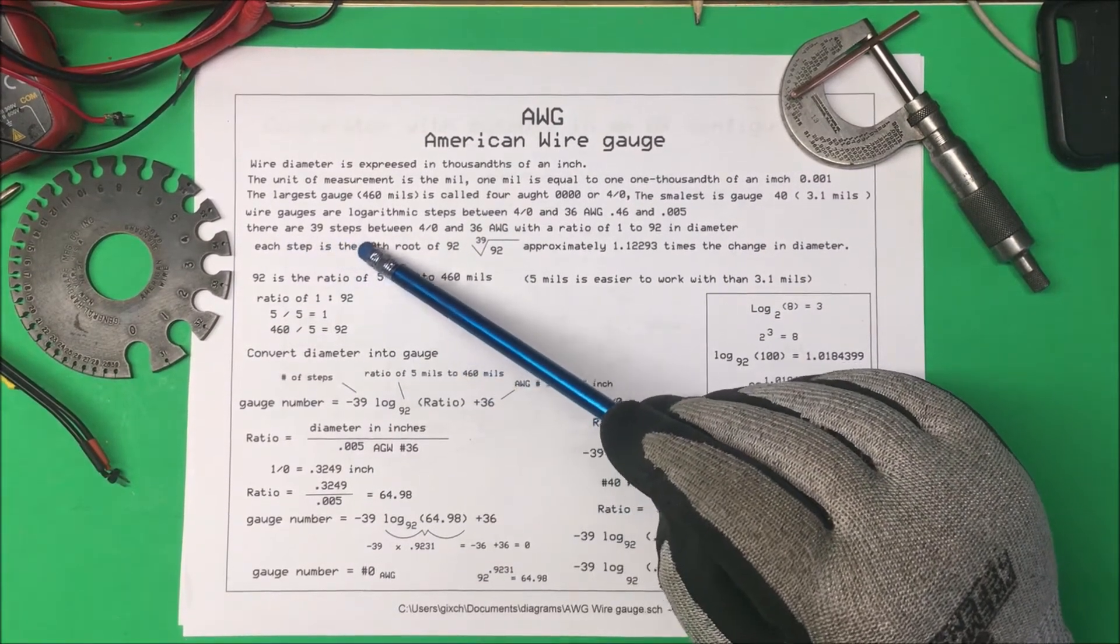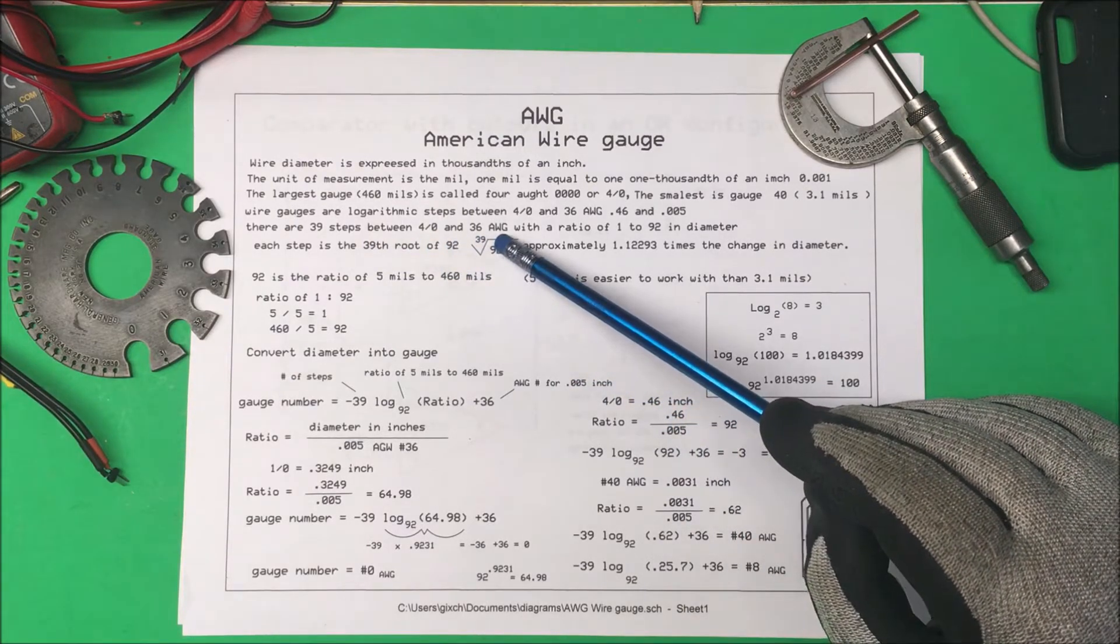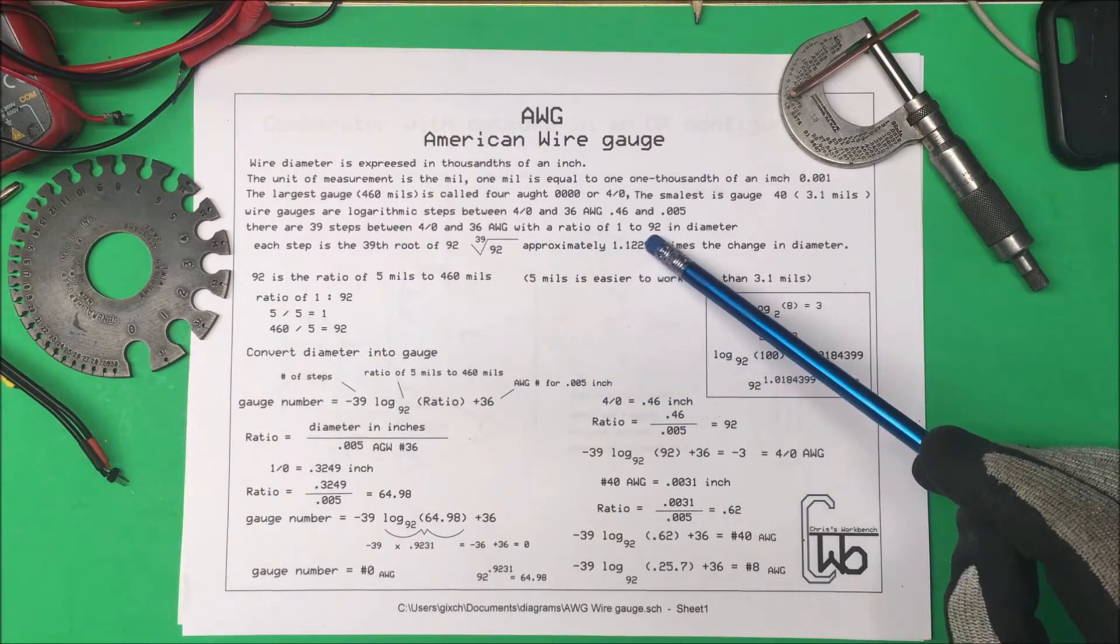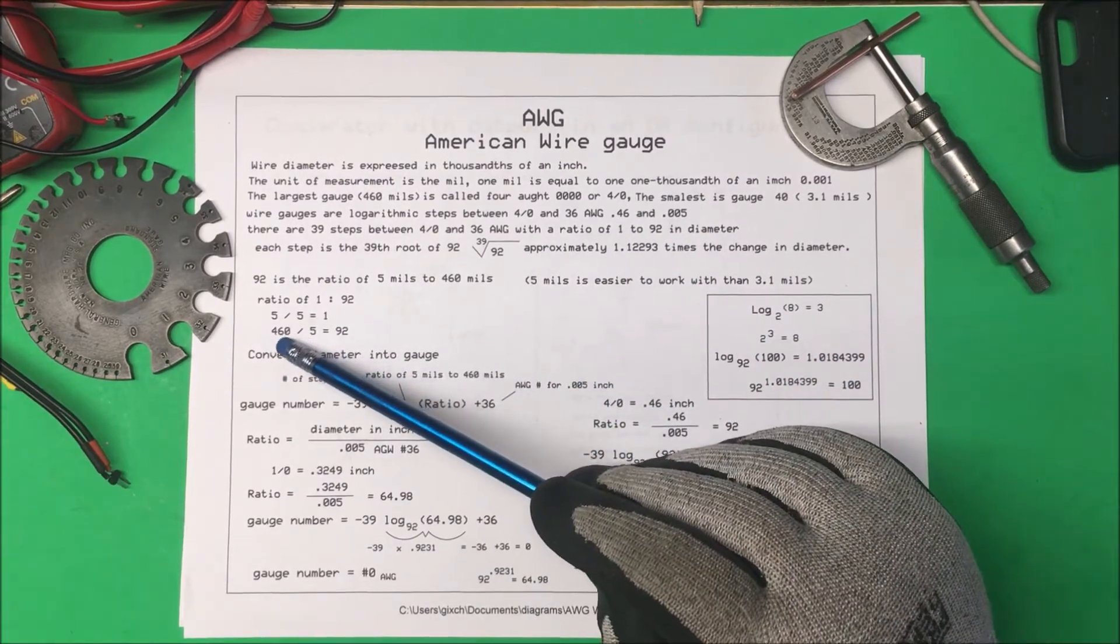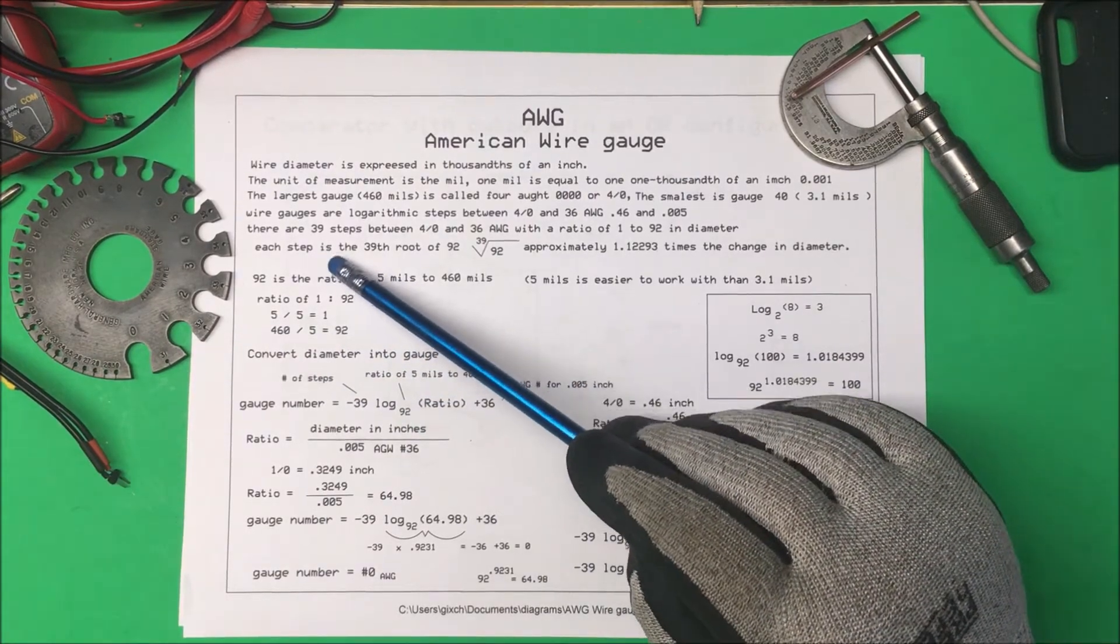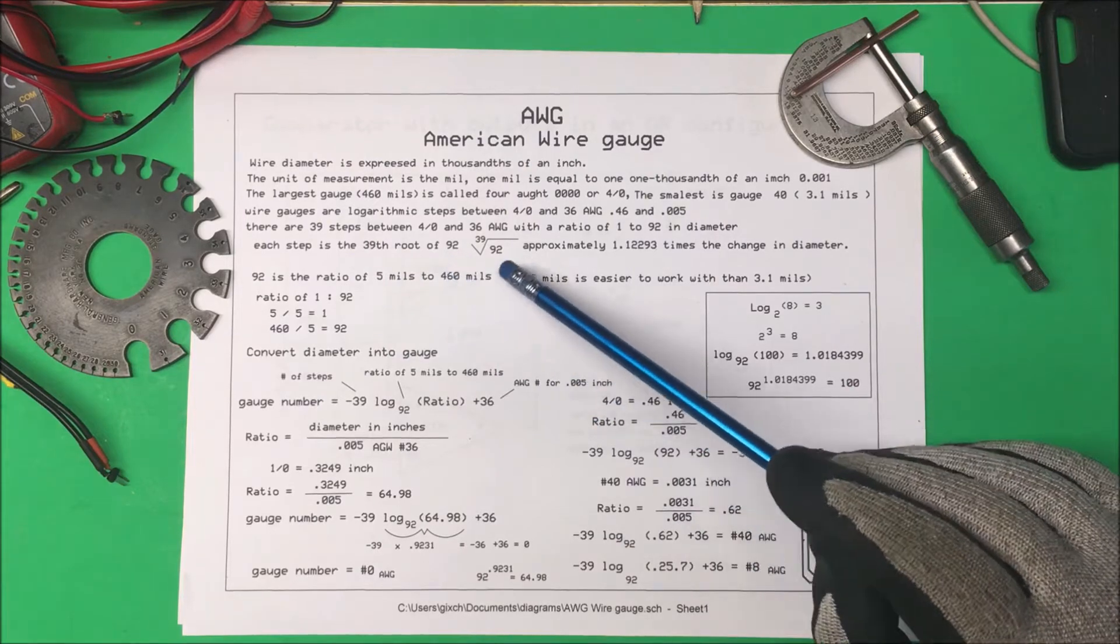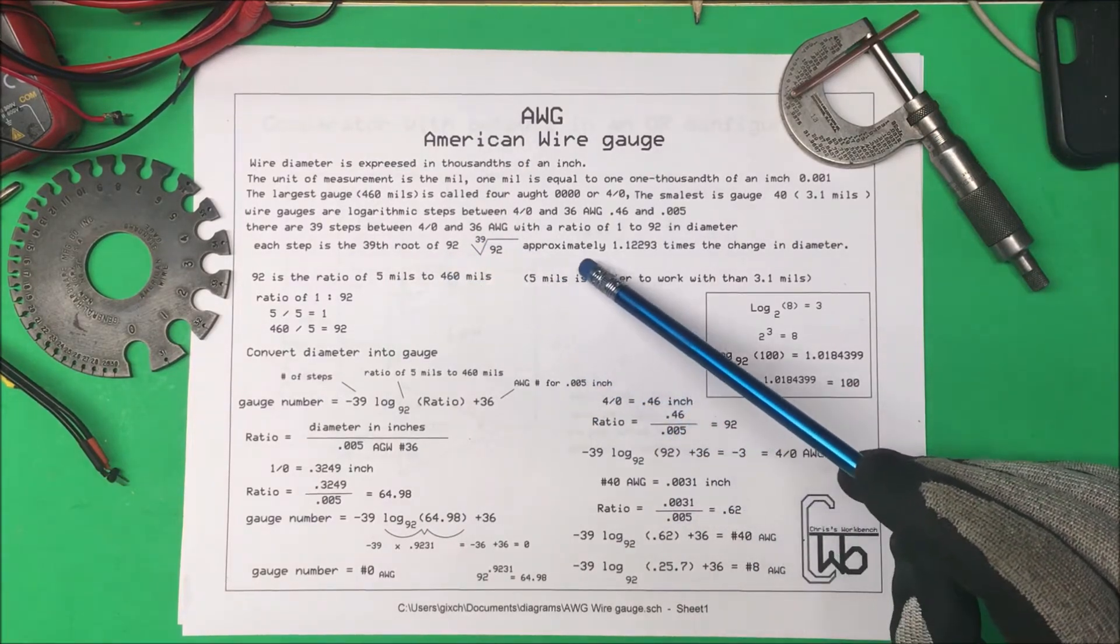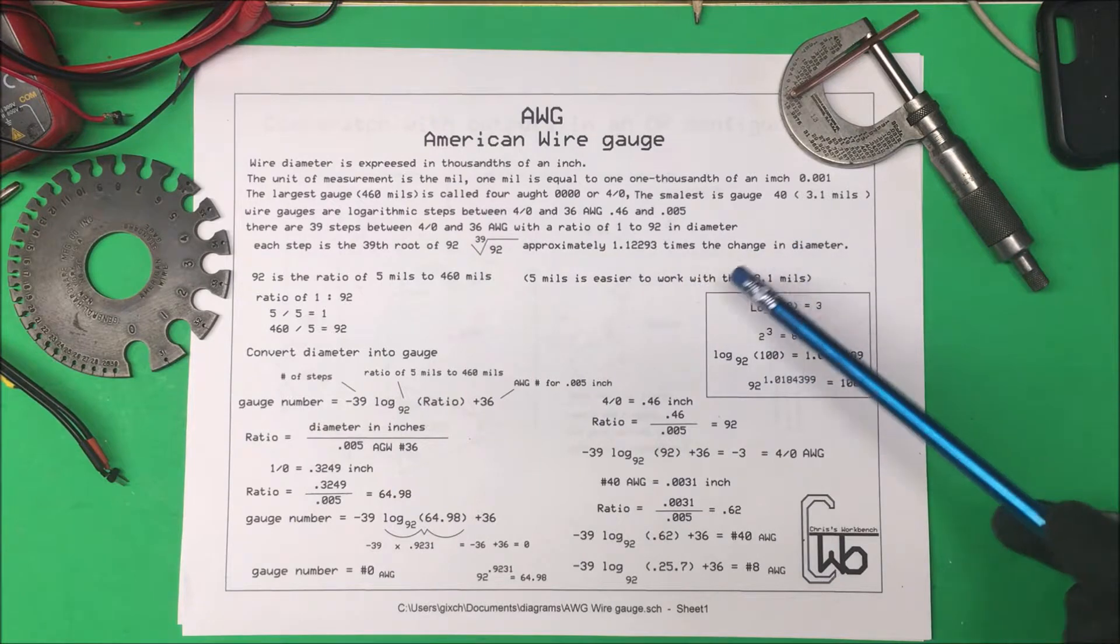There are 39 steps between four aught and 36 AWG with a ratio of 1 to 92 in diameter. That ratio is just 5 divided into 460 that gives us 92 and each step is the 39th root of 92. So it's approximately 1.122 times the change in diameter.